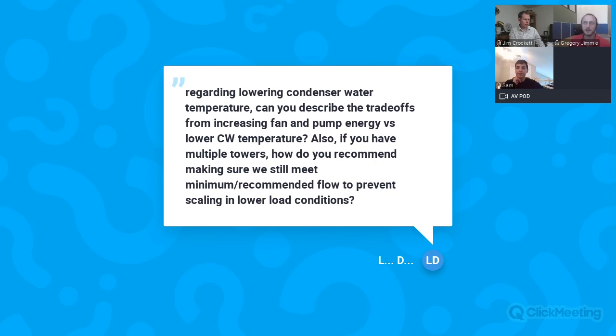Chillers, I would say they typically don't have a full 50% turn down. So definitely check that. That usually can be your limiting factor there. As far as the trade-offs and increasing the fan energy and the pump energy, it's really just look at your math of what's your kW consumed by your chiller and what's the kW being consumed by those cooling tower fans and pumps. As you decrease that condensing water temperature, you'll obviously see those fan powers ramp up. But you should also see your compressor energy go down.